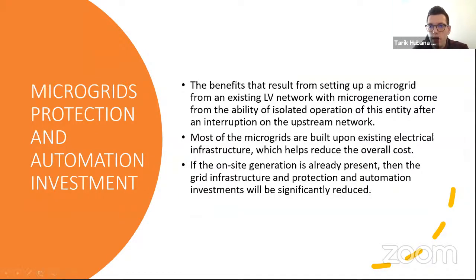But these are some specific cases. What is interesting to us as end consumers, as engineers, and as distribution system operators are the microgrids that are installed in our current low voltage or medium voltage networks. In order to evaluate whether that investment into microgrids is feasible or not, several aspects need to be considered. The benefits that result from setting up a microgrid from the existing low voltage network come from the ability of isolated operation of this entity after interruption of the upstream network. In this case, most of the microgrids are built upon existing electrical infrastructure, which will actually help to reduce the overall cost.